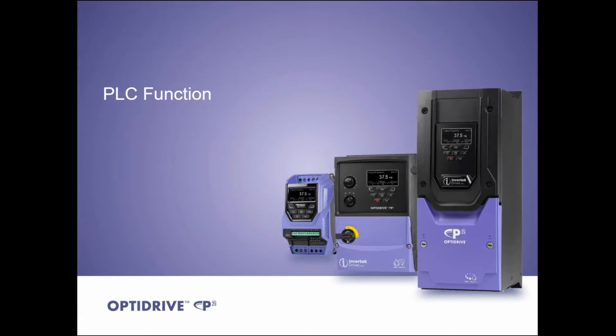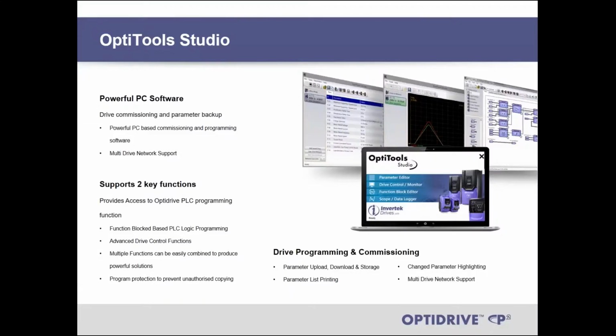And this was the point I wanted to come to. The Optitools has also the PLC functionality for the P2 only, and you can program in function block diagram language. This is the only language available right now. But also the Optitools Studio can be used as a PLC IDE program, as you can see here.